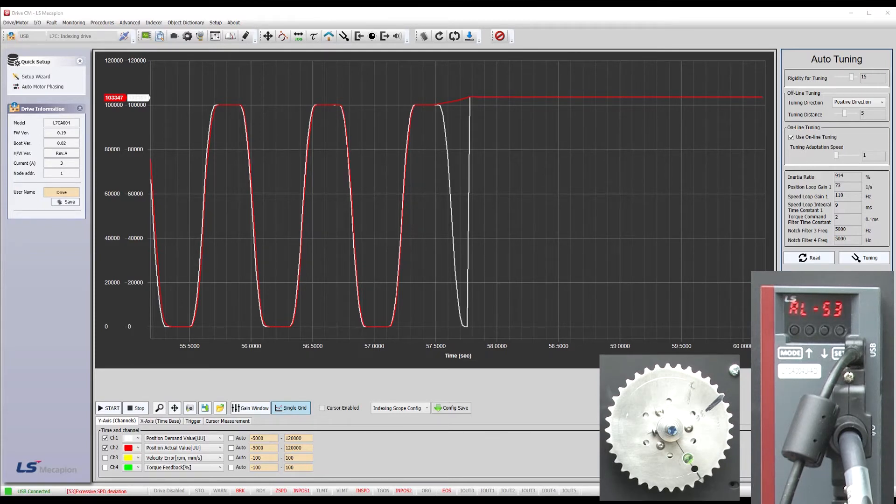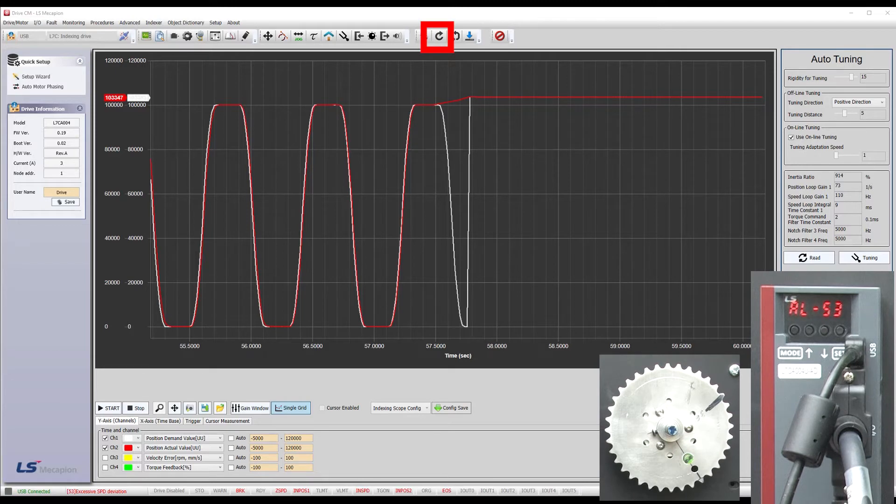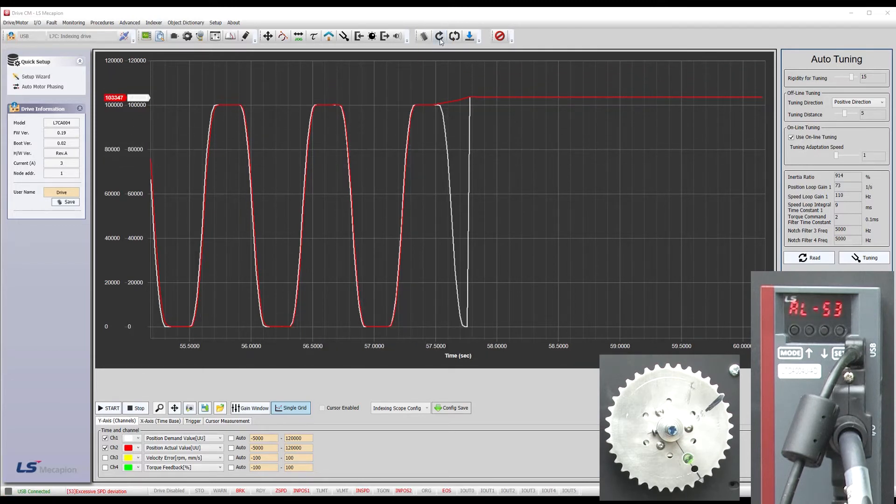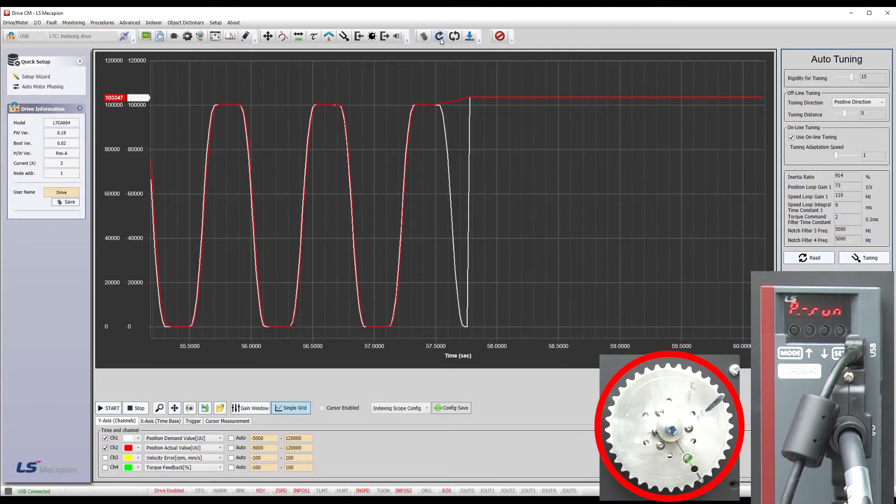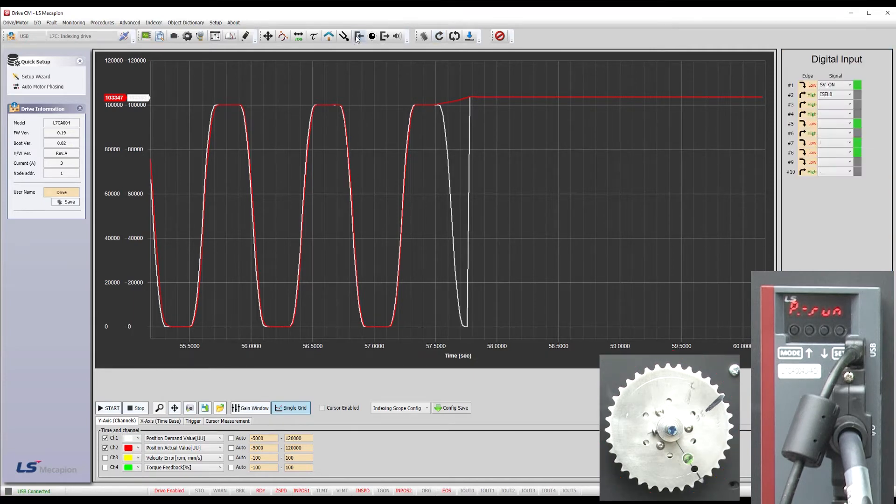One caution, there is another software quirk when doing tuning and indexing like this. Normally, you would simply hit this guy to reset the alarm and continue on. And that does reset the alarm, but the motor isn't moving. In fact, there is no torque at all.